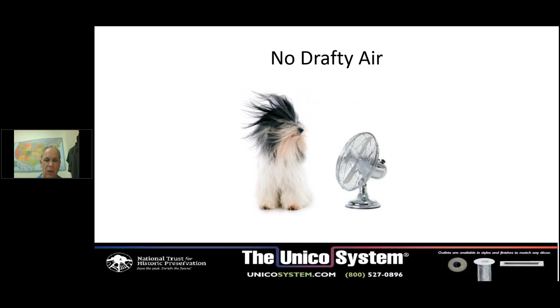So you don't get the 5 or 6 degree temperature variance you get with conventional systems, which work on a much different basis. We put small volumes of air in at a fast pace in a couple of places in a room. Conventional generally has one big grill in the room where they put all the air, so they dump 70% of the air they're putting into that room into 25 or 30% of the space. If you're near that, you get a terrible draft and you're very uncomfortable. If you're 10 feet away, you don't feel it, you're gonna feel cold, you're gonna complain.